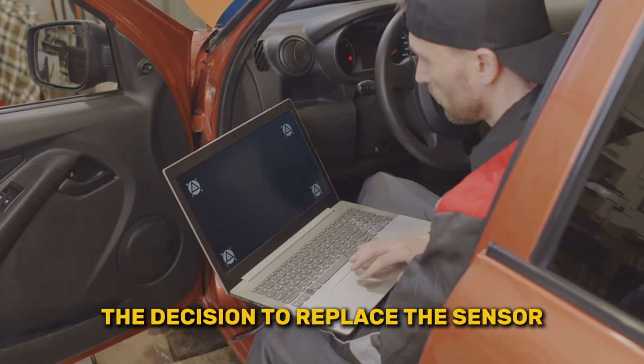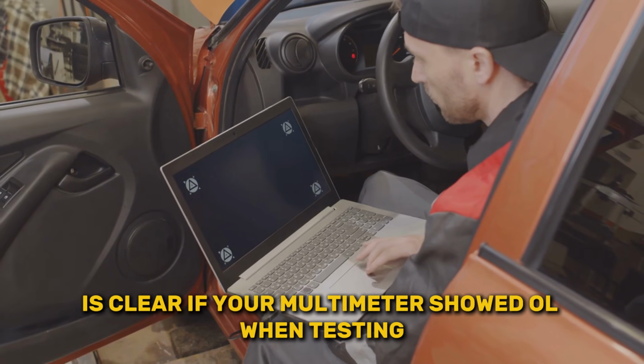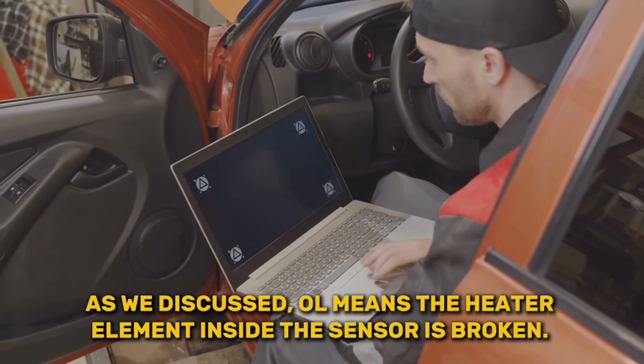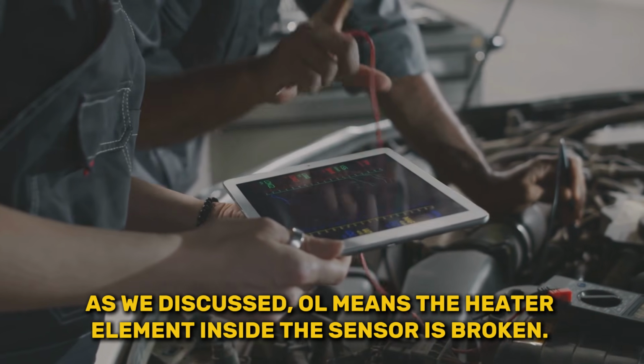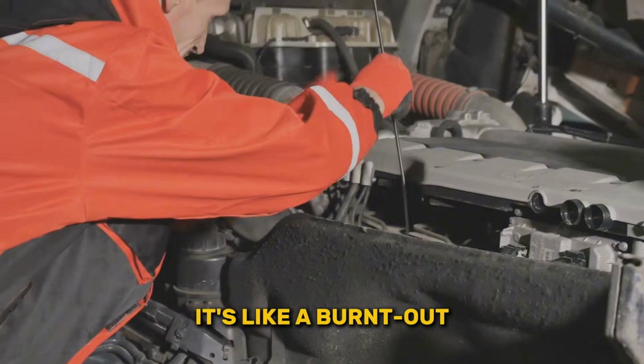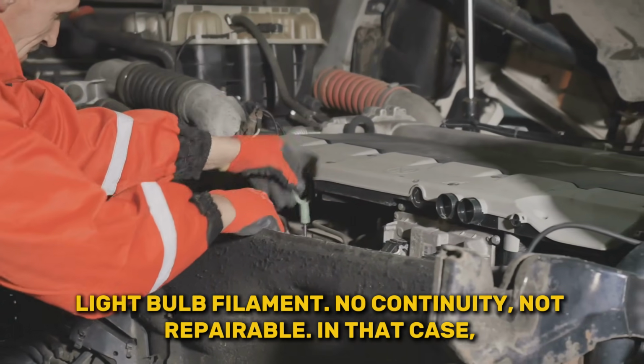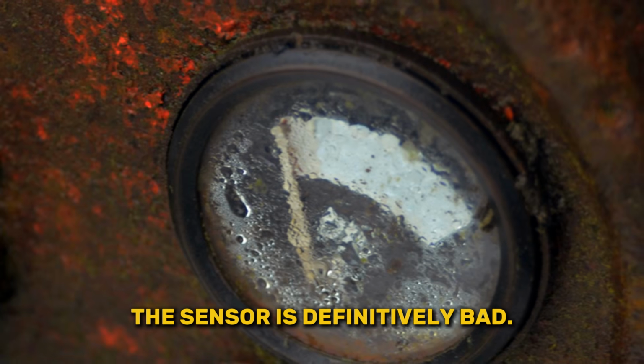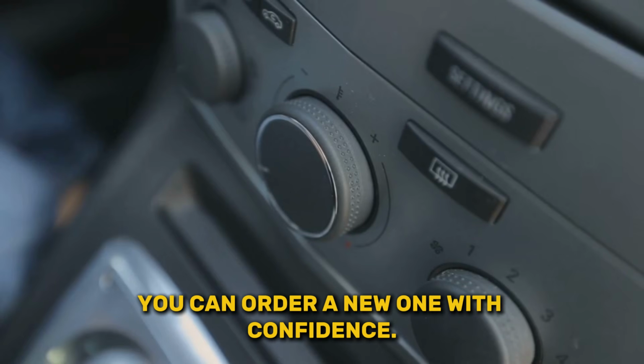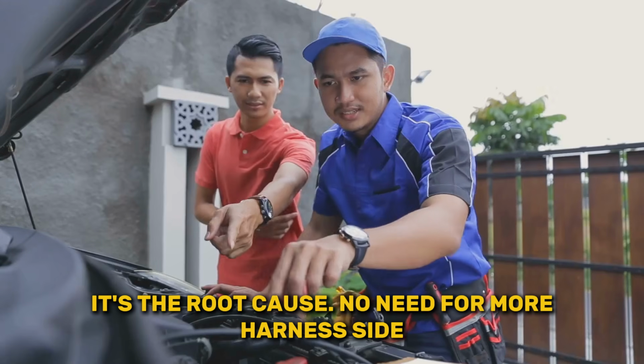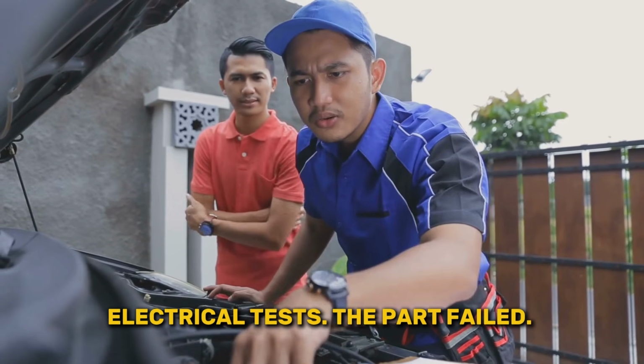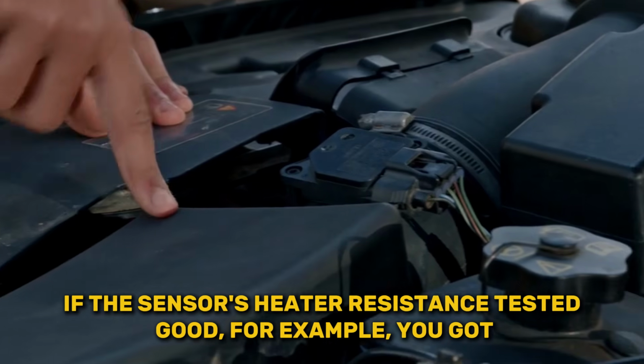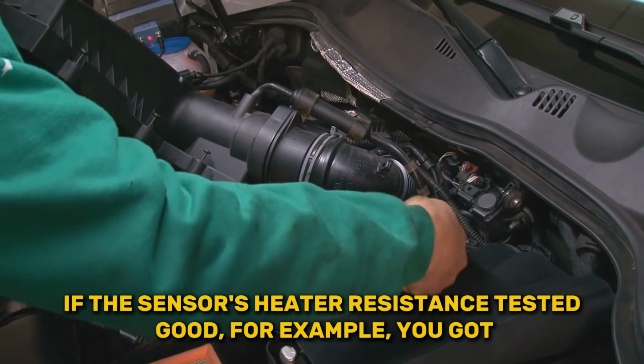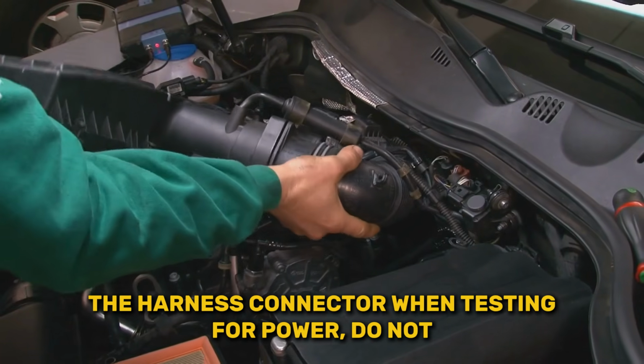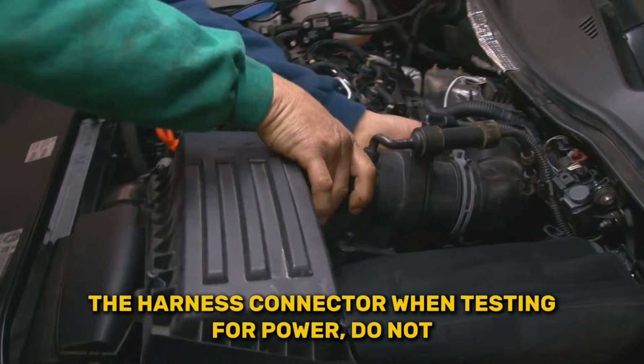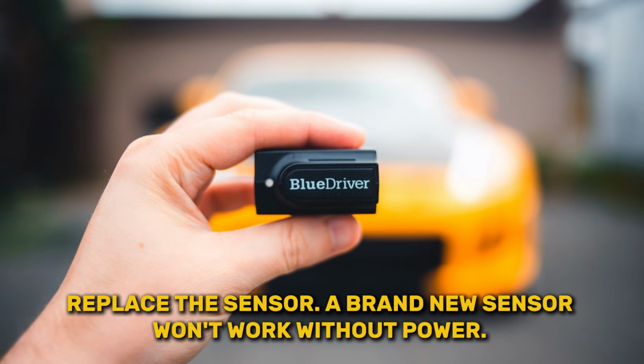The decision to replace the sensor is clear if your multimeter showed OL when testing the heater pins on the sensor itself. As we discussed, OL means the heater element inside the sensor is broken. It's like a burnt-out light bulb filament. No continuity, not repairable. In that case, the sensor is definitively bad. You can order a new one with confidence. It's the root cause. No need for more harness-side electrical tests. The part failed. If the sensor's heater resistance tested good, for example, you got about 8 ohms, but there is no voltage at the harness connector when testing for power, do not replace the sensor. A brand new sensor won't work without power.